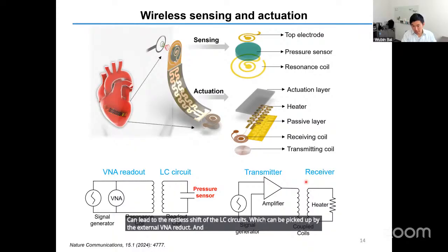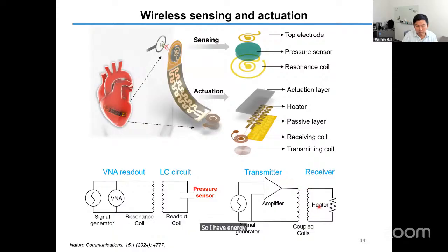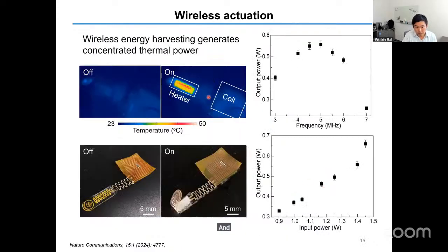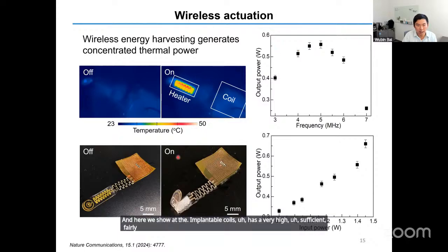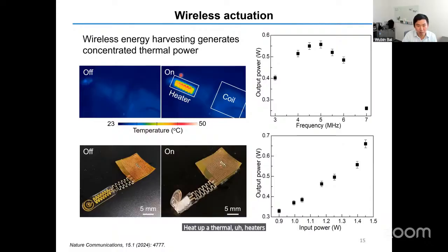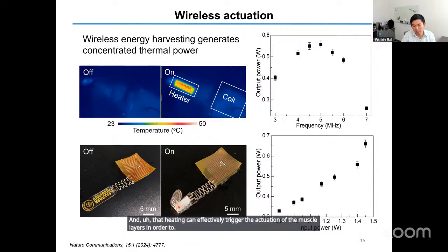And similar to the energy receivers, if we apply a coil-based energy source, it can efficiently transmit the RF energy into the receiver coils that connect with the implants in order to provide the energy to enable stimulation. In this case, it's a thermal stimulation based on electrode heaters. And here we show the implantable coils have sufficiently high energy receiving capabilities, which can heat up the thermal heaters, as shown from the heat maps, and that heating can effectively trigger the actuation of the muscle layers in order to bend the structures on demand.